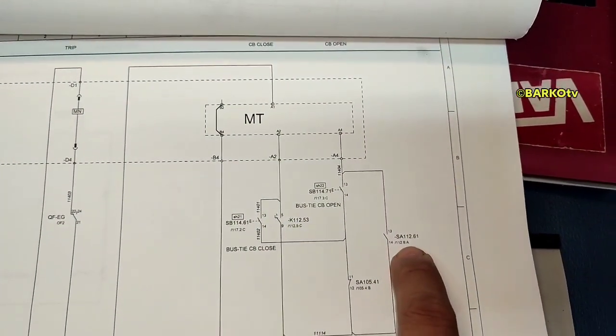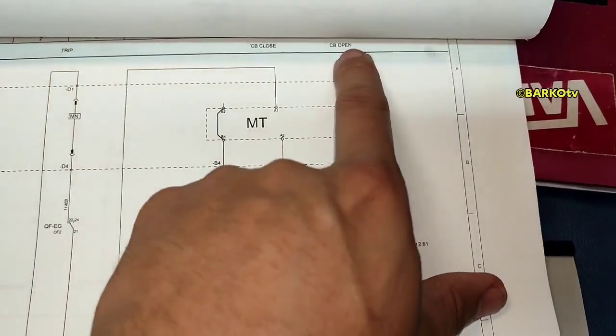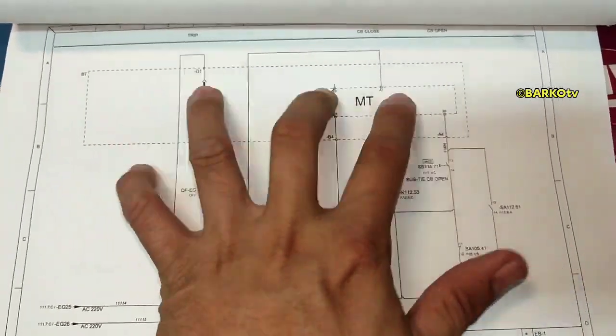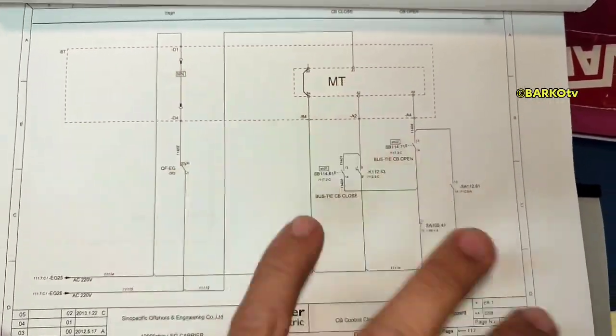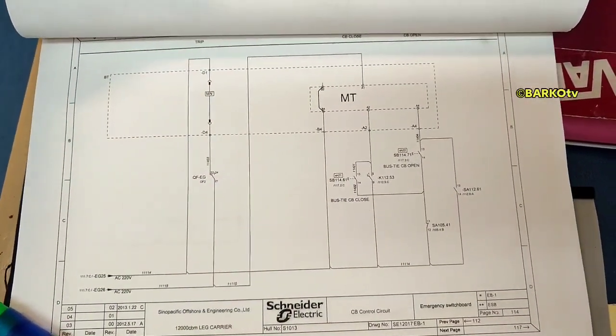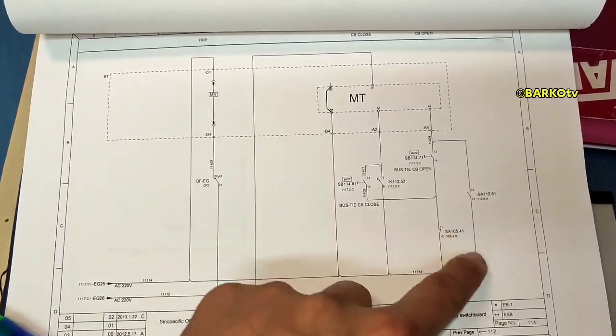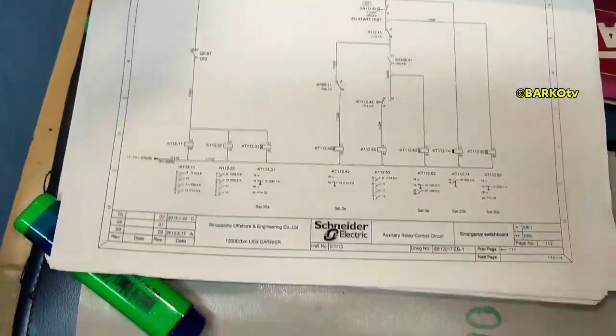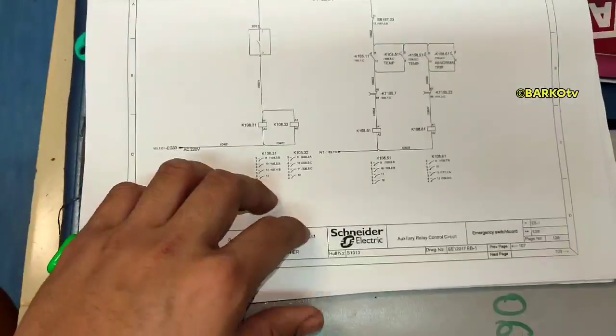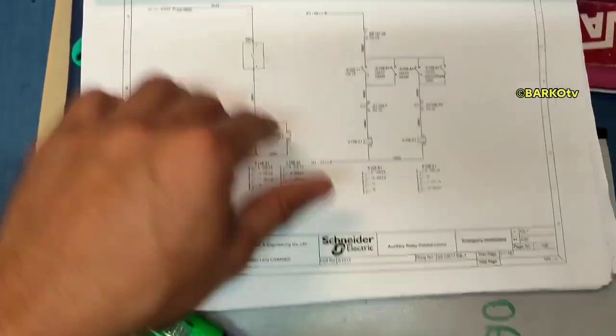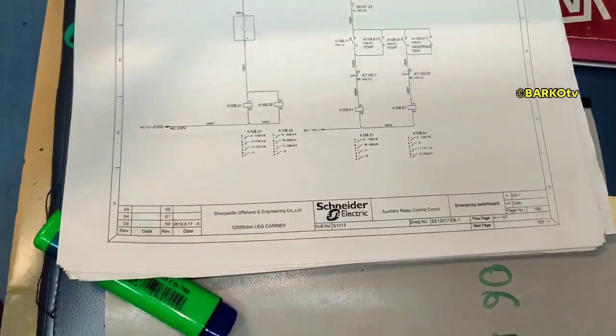This contact will close and then that contact will close — that is for the CB open command. CB open refers to the bus tie, because this belongs to the bus tie circuit. It means the bus tie breaker will open, and after it opens it commands the emergency generator to run. There is a bus tie and emergency ACB breaker — this is the bus tie open command.